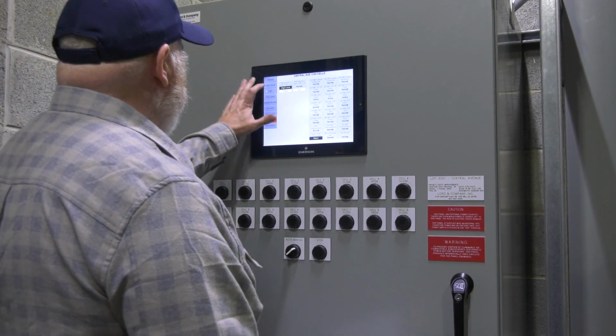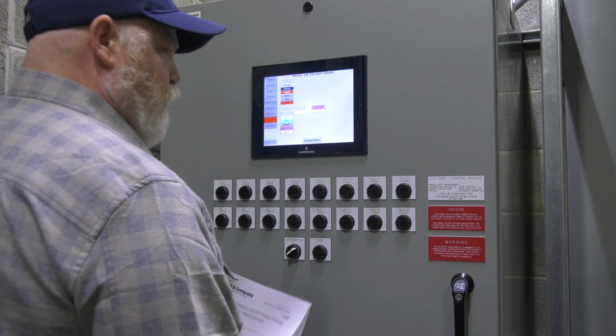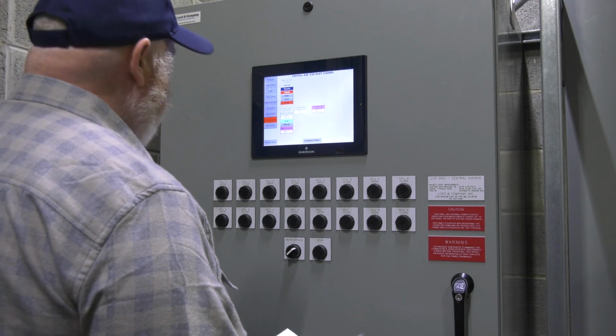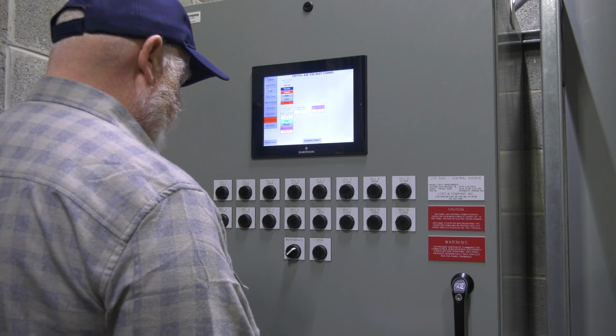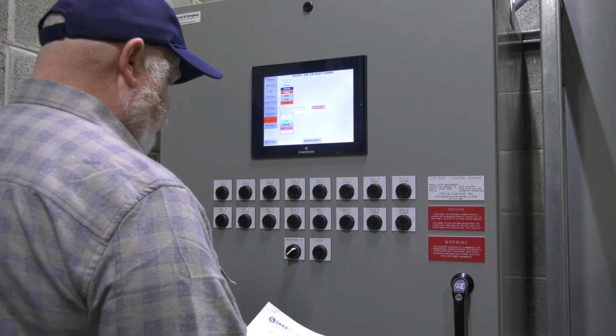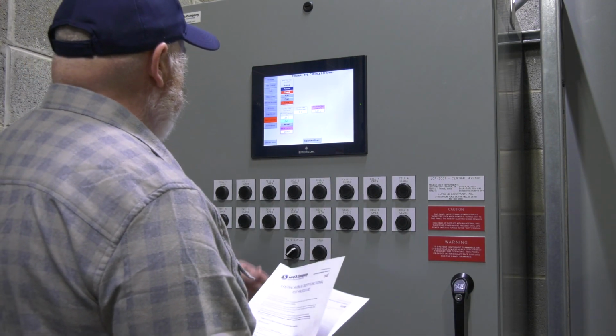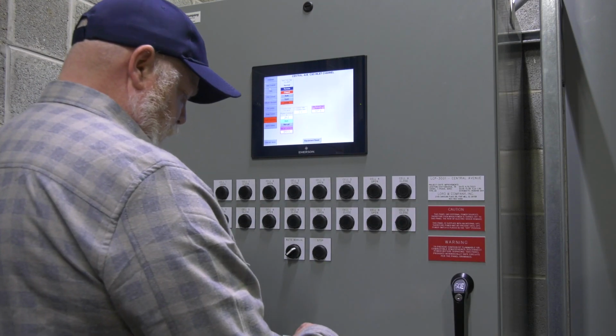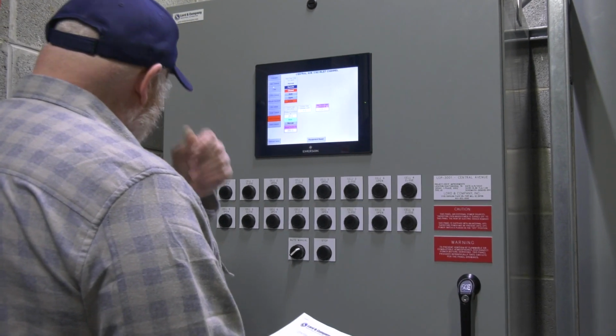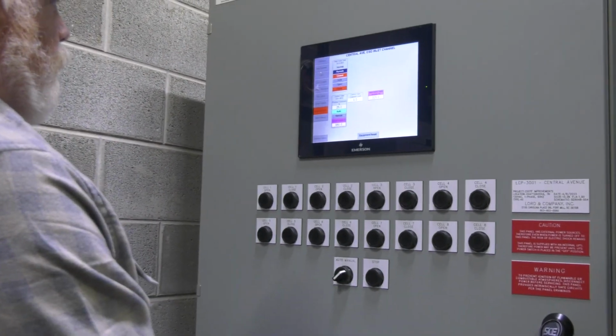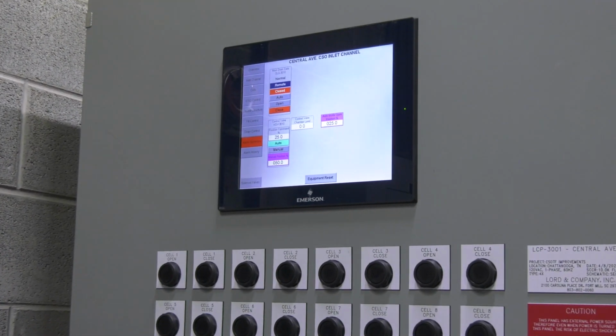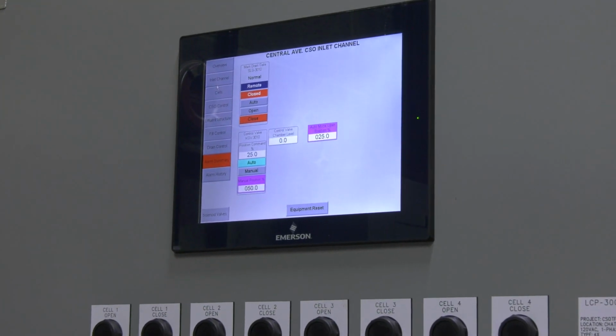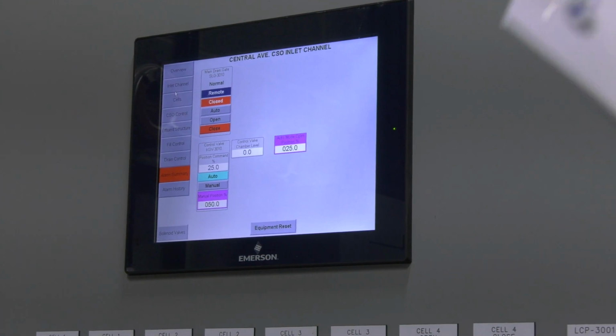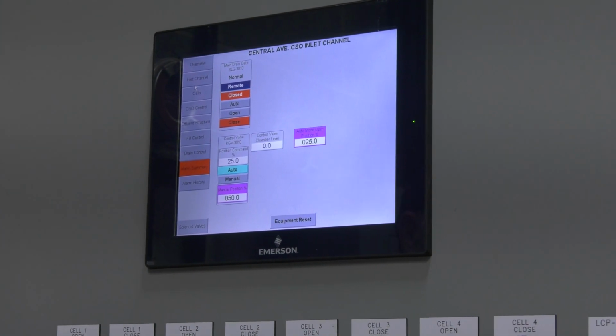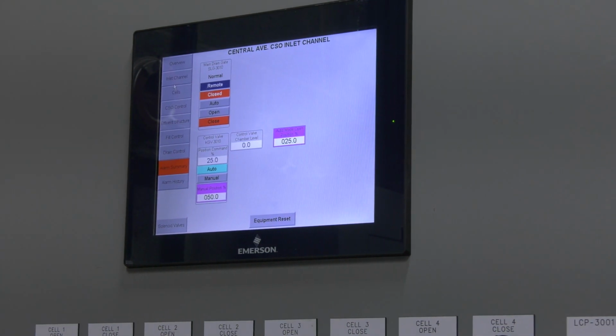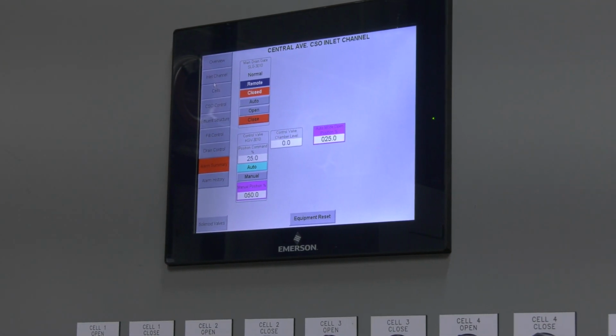All right, so let's see. When the old one was running, the level in the influent would rise, and it would trigger the CSO to close, correct? Yes. Now we're working off of influent level, correct? Well, with the way I run it now, I've got all my CSO gates down there closed. And the diversion gate back here, since it's not tied in to this, does its own thing. So we just let it do its own thing and keep the CSO closed.